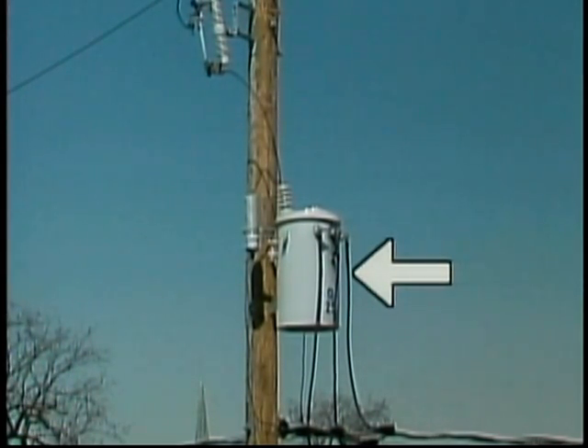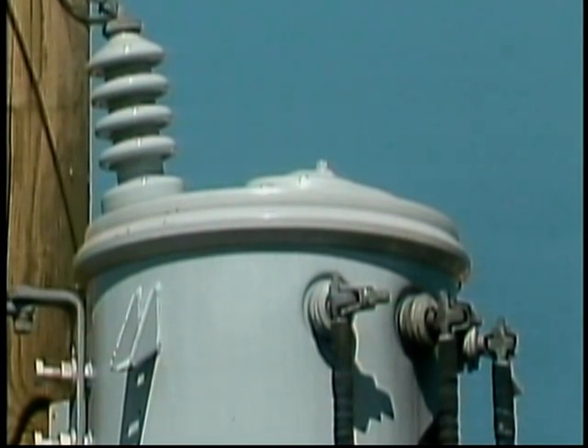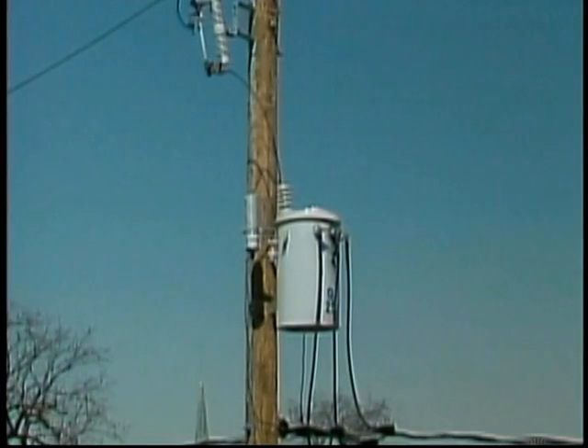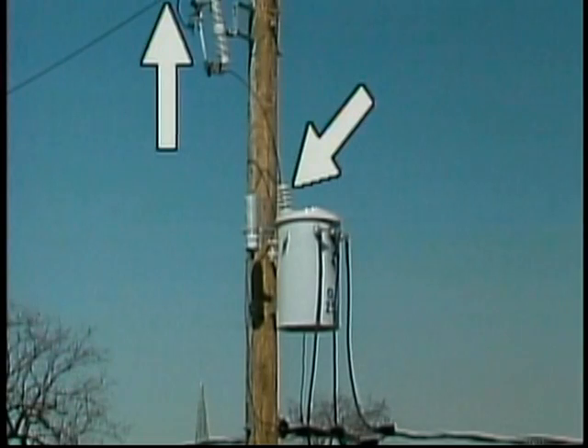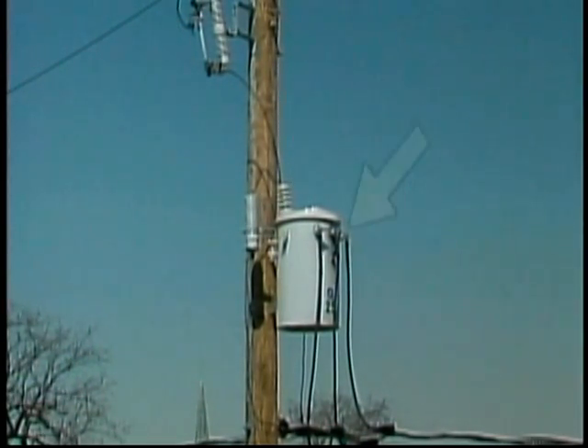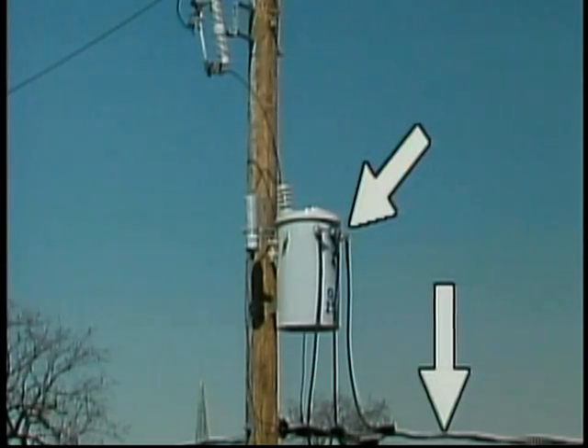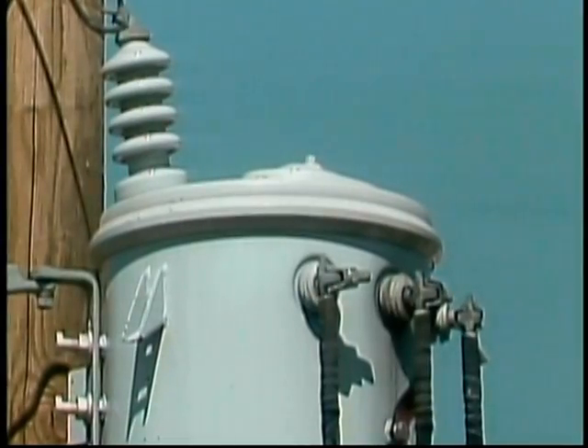It's cylindrical in shape, and because it steps primary voltage down to secondary voltage, it has different sized bushings. A distribution transformer has one or more larger bushings and several smaller bushings. The larger bushing insulates the transformer connection to the higher voltage primary circuit. The smaller bushings insulate the transformer connections to the lower voltage secondary circuit. The presence of two different sized bushings is a key feature to recognizing a distribution transformer.